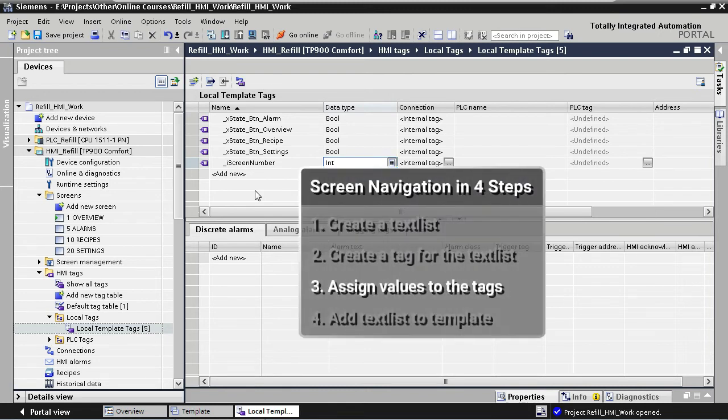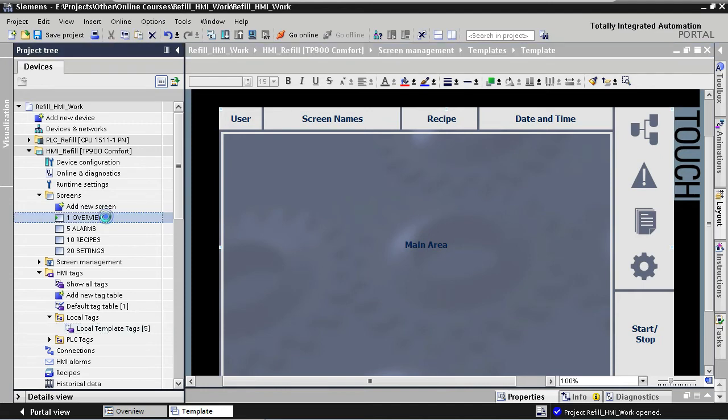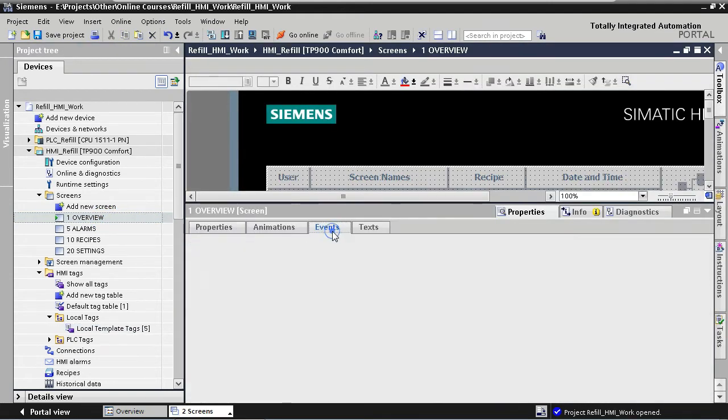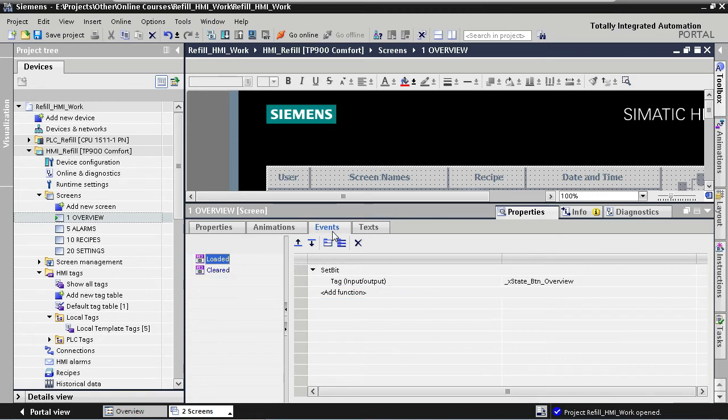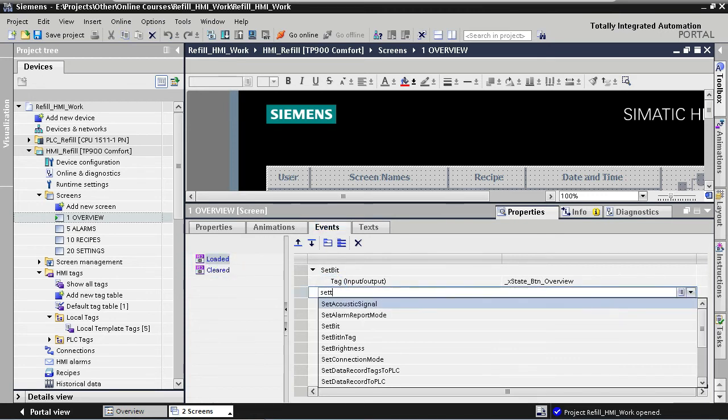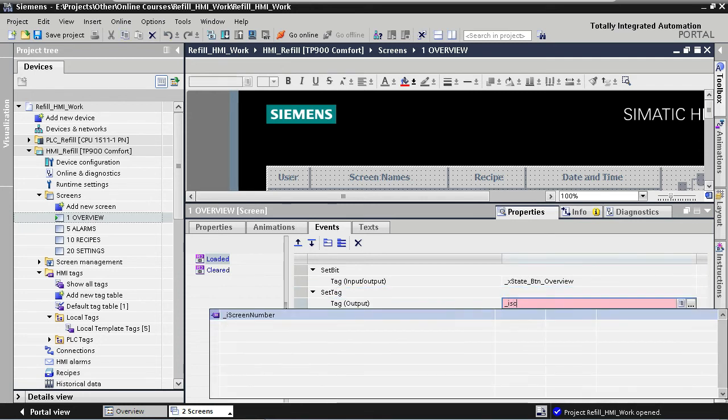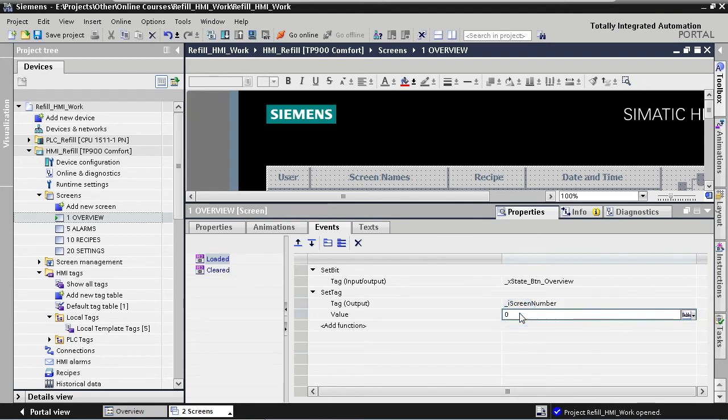In our third step, we are going to set the correct value for the tag depending on which screen is loaded. We start with our overview screen. Here we go to events. And under the loaded event, we are going to add a new function that will assign a value to our tag. The function for setting a value to a tag is called setTag. The tag that we want to use is the tag that we've created in the previous step, and the value that we want to set our tag to for the overview screen is the value 0.